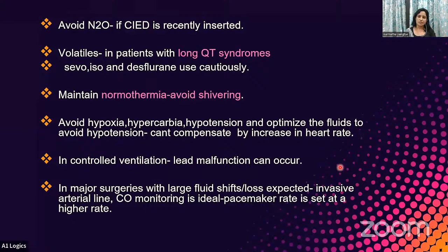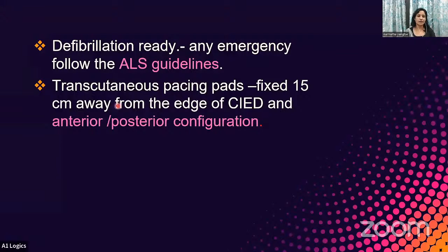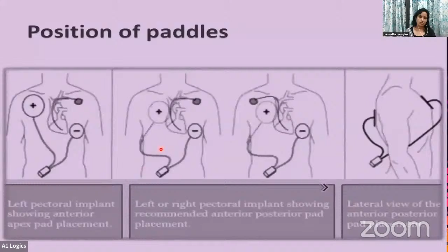And in a case of major surgery where you expect large blood loss, better you ask the programmer to set the pacing rate at a higher level. Then OT should be ready with the defibs and the temporary pacing pads. And while pacing, these temporary pacing pads should be fixed 15 centimeters away from the edge of the CIED and in the antero-posterior configuration. The shock should pass perpendicular to the CIED leads. So this is the position of the paddles you have to place.